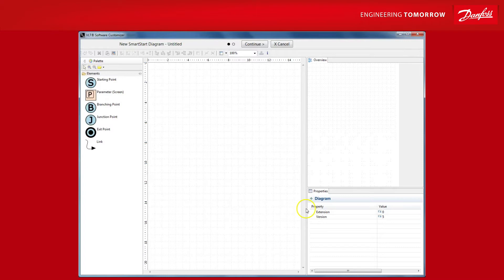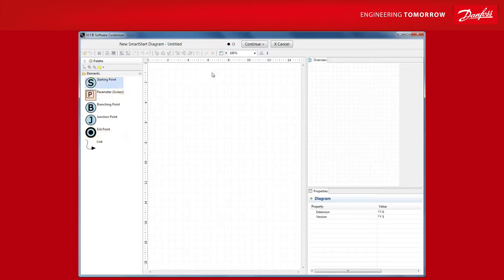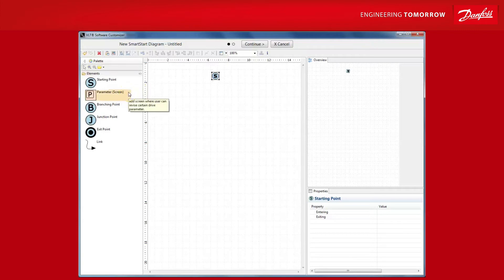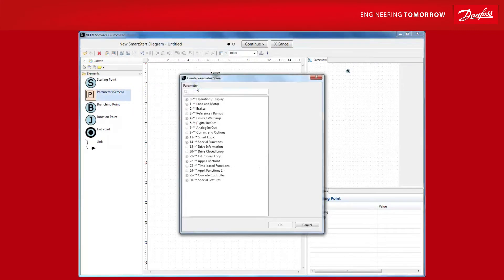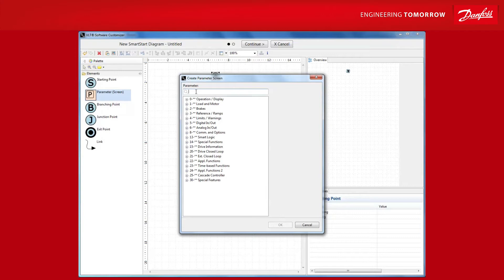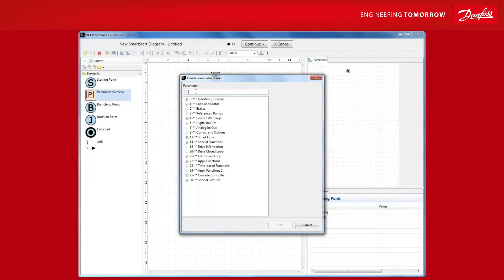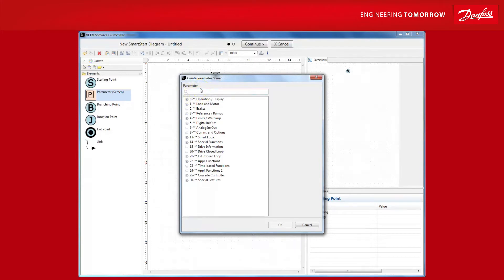Simply drag and drop it onto the canvas and then let's go for the first parameter for which you want the drive to prompt the user for the value or selection for. Once I drop the parameter element onto the canvas, the SmartStart editor asks for the parameter selection. It's often a good idea to start with the display language. You can either type in the name in the filter field or you can browse through the menu structure if you are uncertain about the naming of a particular parameter.